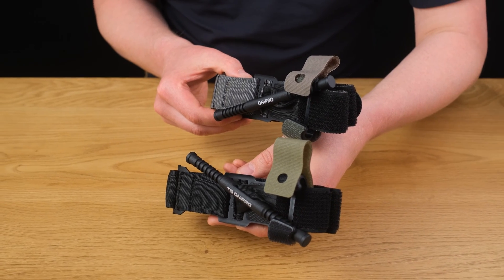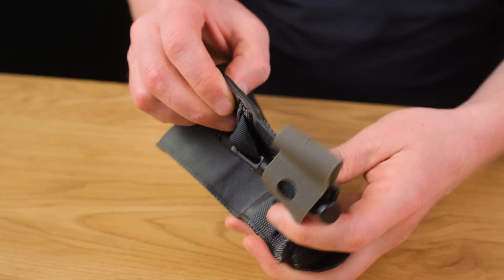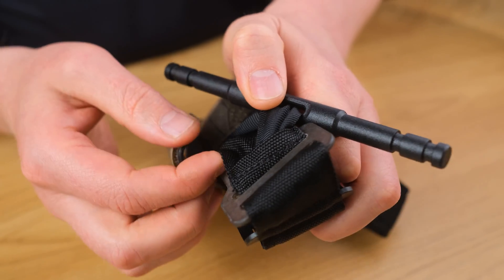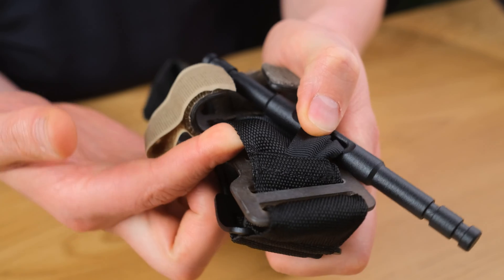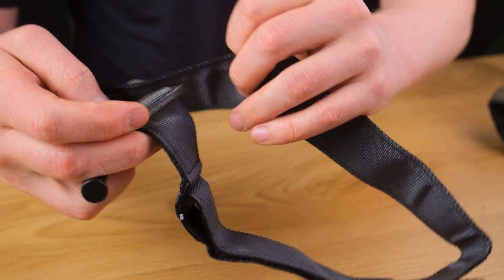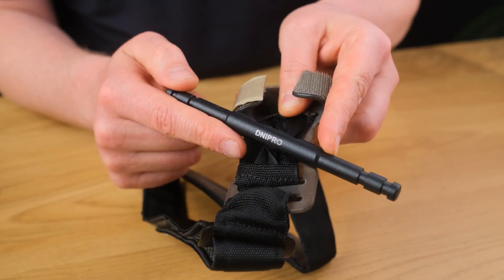The transition to the second generation has been marked by the following changes: the design of the isolation platform was changed, though the material remained the same, and the segmental hook-and-loop tape was replaced with hybrid hook-and-loop tape. The transfer of the outer band — part of the tourniquet cover — from the upper isolation platform to the lower part was one of the most important design changes. This solution protected the device from the possibility of a very dangerous phenomenon where the outer band is tightened by a knot formed by the rod of the wind-up device.